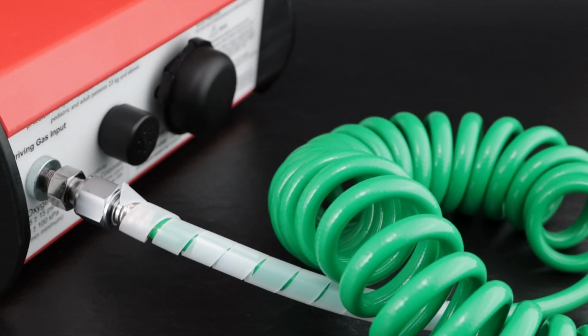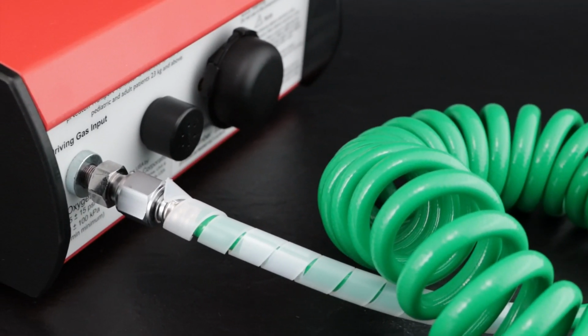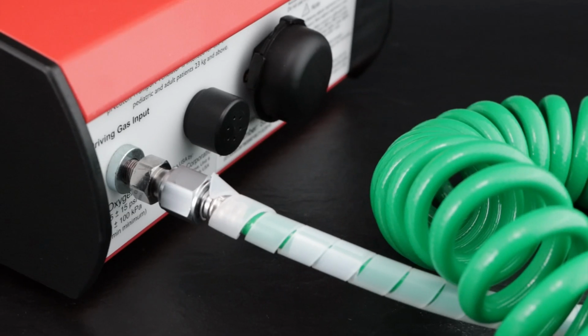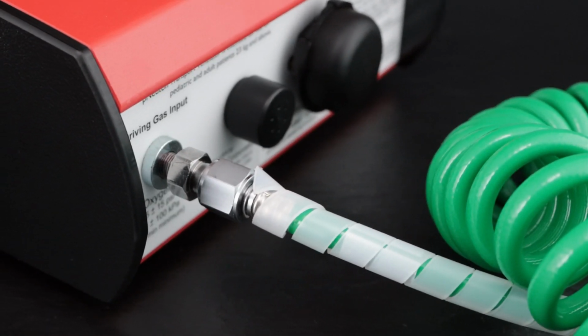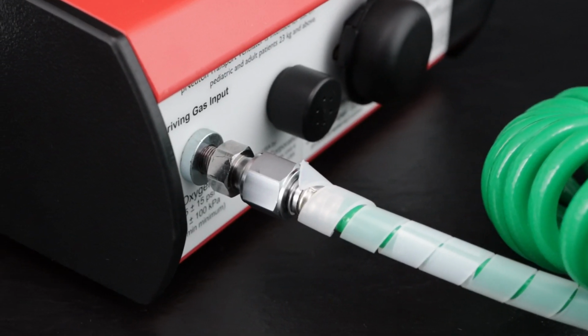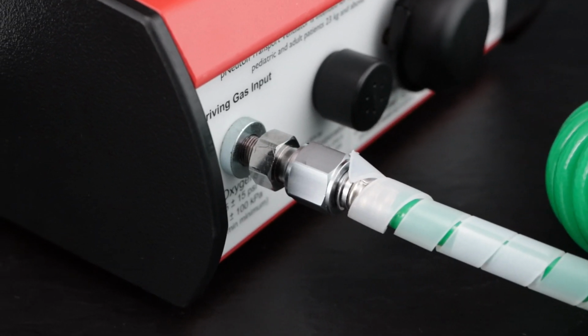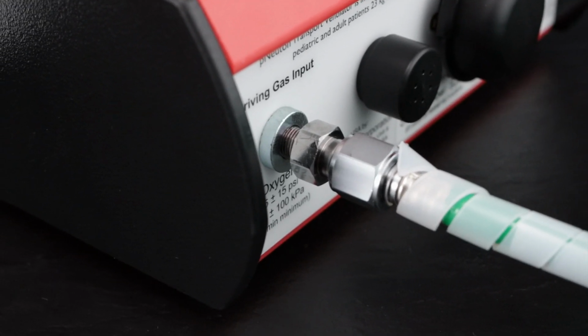Always ensure that the gas supply line is secure and operating at the proper pressure. Note that when gas is first connected and flowing, the ventilator will alarm. This is normal. The ventilator will begin to function at the preset values.